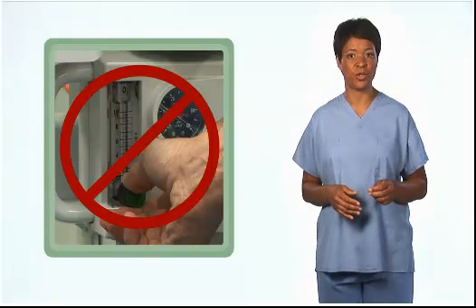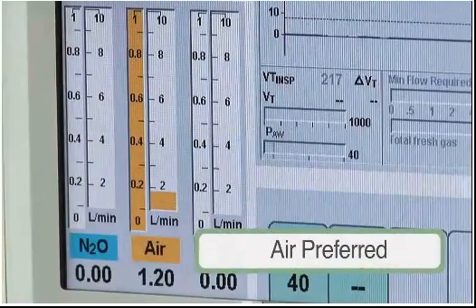When delivering oxygen by nasal cannula or mask in such exceptional cases, you should not use the auxiliary oxygen flow meter, which is only capable of delivering 100% oxygen. The goal is to deliver the minimum concentration of oxygen necessary to maintain adequate oxyhemoglobin saturation. Restricting the delivered oxygen concentration to 30% or less will minimize fire risks during exceptional surgeries, but room air is preferred whenever possible.